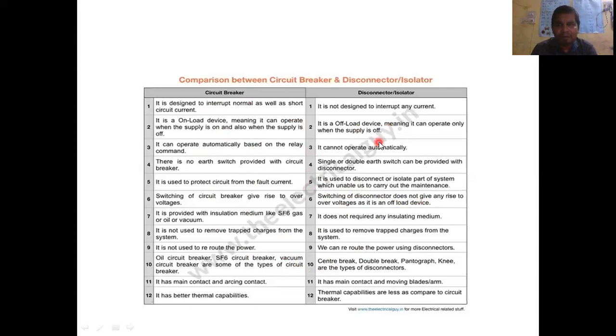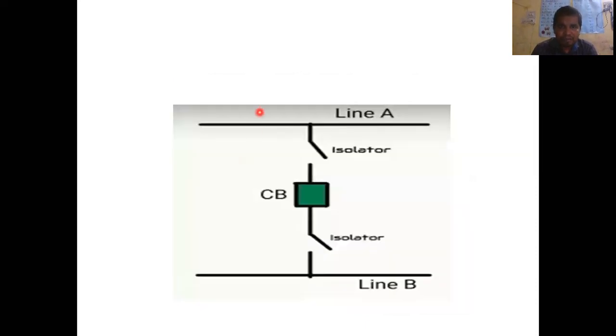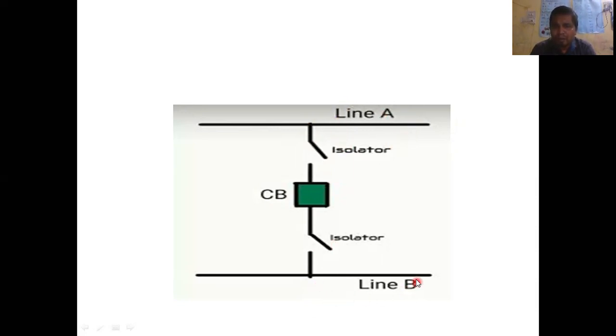The isolator is not automatic — it is manual and used for maintenance purposes. The circuit breaker protects the circuit from fault current; when a fault occurs, the relay sends information to the circuit breaker, which disconnects the fault section. The isolator is used to disconnect or isolate a part of the system to carry out maintenance. Switching off the circuit breaker can give rise to overvoltages, but switching the isolator does not give rise to overvoltage as it is an off-load device. For example, when you want to do maintenance work on a line, you disconnect it using the isolator, and the circuit breaker is separately present for fault protection.